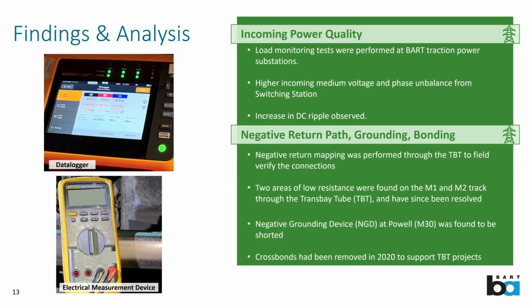And there are additional loggers. Bart took some proactive measures before the Parsons team started to install DC loggers. So similar to the AC loggers that were installed through this investigation, there were DC loggers looking at the output of the substations. The power quality analyzers that were installed were to look at the AC side coming in. So that gives our team a complete picture, and that data is currently being analyzed. In fact, those power quality analyzers are still in place at the MTW substation. They were installed on the East Bay side at KPS and on the West Bay side at MTW.